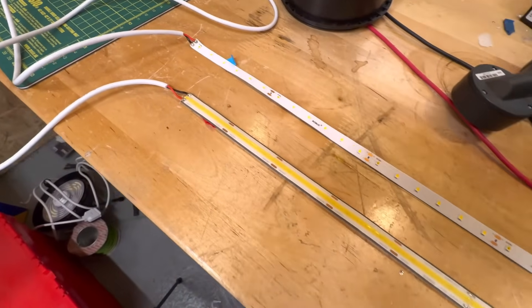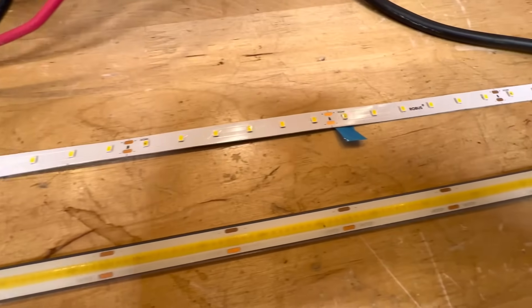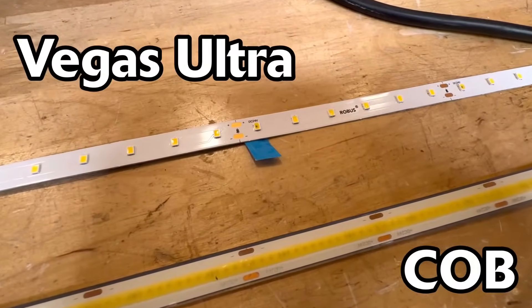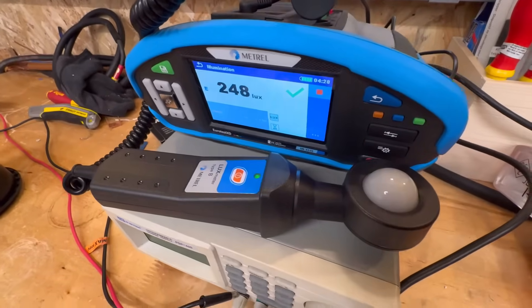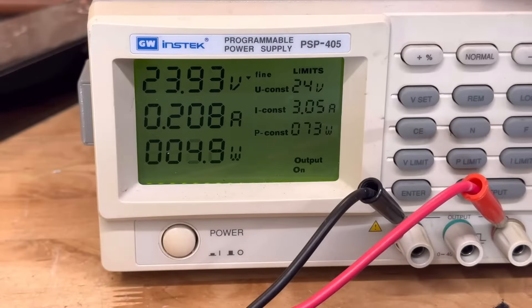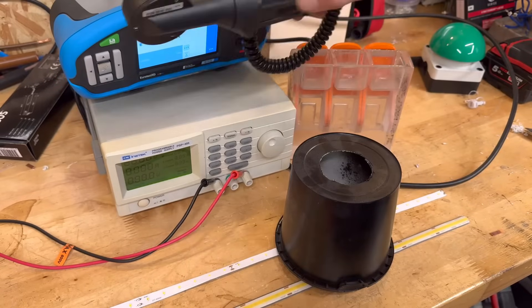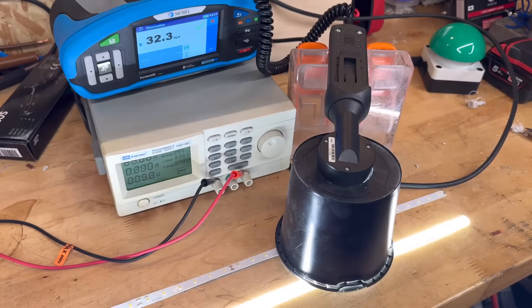Laid out on the bench here are two different types of strip — they both run on 24 volts. One of them is the Vegas COB from Robus; for more information on COB strip see a previous video in this series. The other is the Vegas Ultra. This particular variant of COB strip has a maximum length of 10 meters, although a length of 5 meters is more common. Rather than connecting up long lengths of strip and measuring volt drop versus light output, we've hooked our strips up to a DC power supply where we can control the voltage to mimic the volt drop. Taking the COB strip first, we start off at the full 24 volts and the light output is hovering around the 1,870 lux mark.